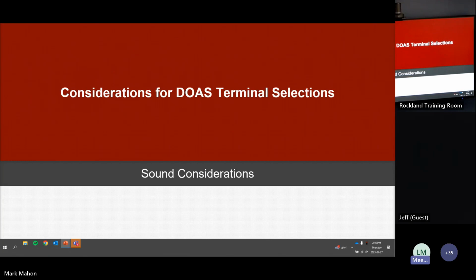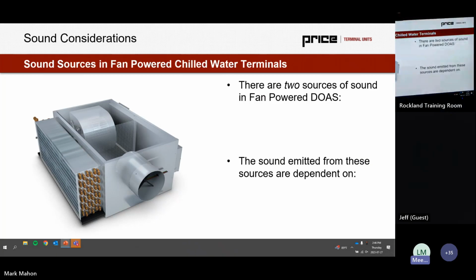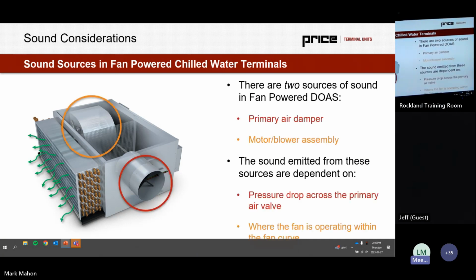So quickly here, I want to talk sound considerations. And the big thing for sound considerations for any product that has a coil and a large return opening is there's going to be multiple sources of sound. They're going to drive acoustics, and they're going to be very close to a big hole in the casing of the unit. So if we see a coil, think of that coil as a hole for sound to travel through as well.